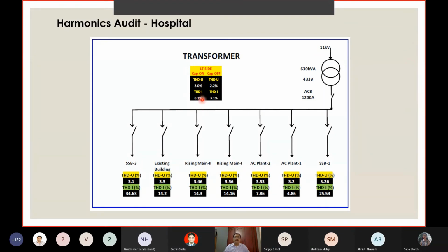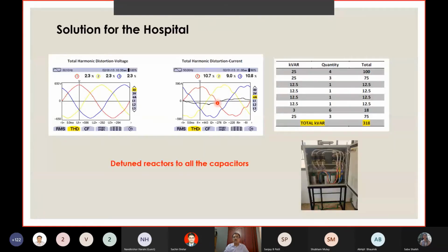Yeah. So when the capacitor was on, the THDI was measured as 8.1. See, TDD will be less than THD, so we did not caution the customer to reduce the harmonic limit. But then what we found out was when the capacitor is switched off, the same THDI value comes down to 3.1. I have a couple of slides as to why this happens. We'll discuss that. But what we gave this customer as a suggestion is to go for detuned reactors. Instead of having plain capacitors, we suggested they have reactors and capacitors in series so that they will be able to reduce the harmonics. At one particular point in time, we also found out, this was another occasion when we did this analysis, the harmonic was 10.7, 9 and 10.8%. So detuned reactor alone was the recommendation made to this facility.